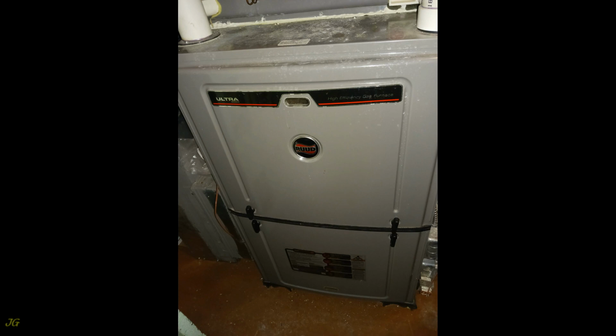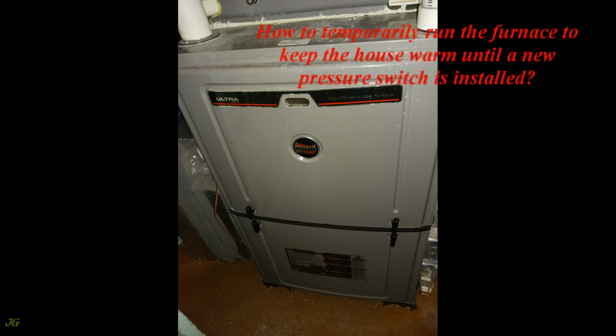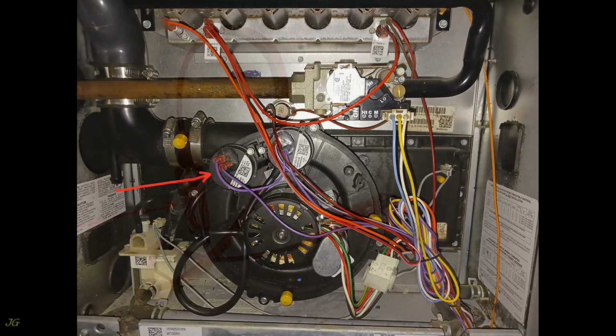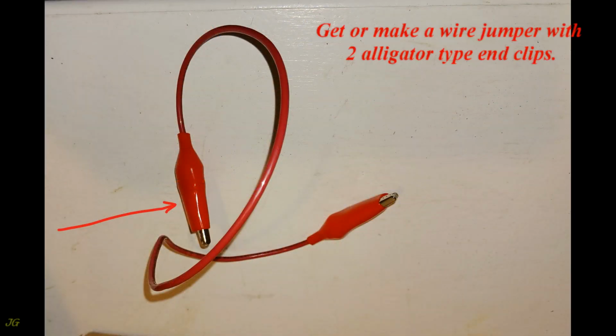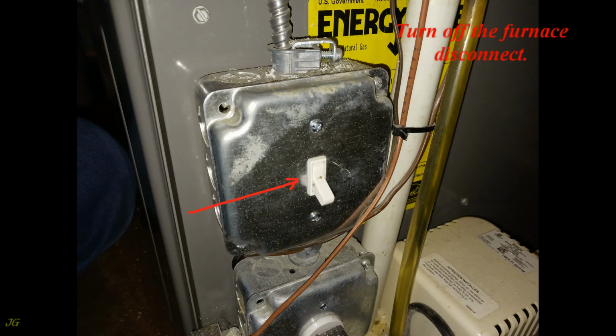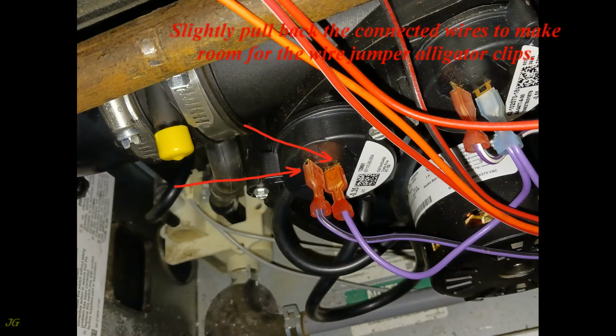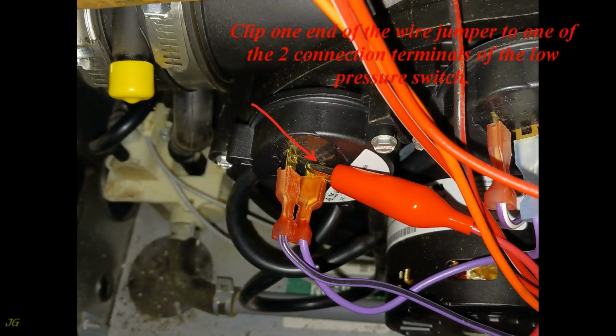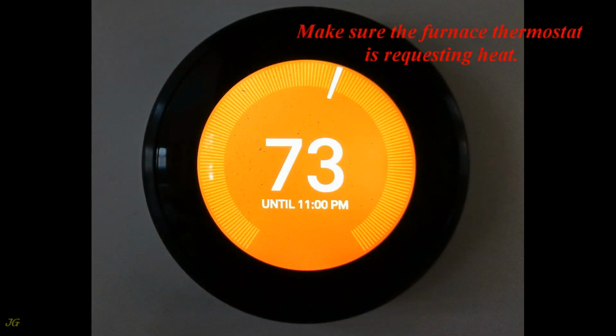How to temporarily run the furnace to keep the house warm until a new pressure switch is installed. Get or make a wire jumper with two alligator type end clips. Turn off the furnace disconnect. Slightly pull back the connected wires to make room for the wire jumper alligator clip. Clip one end of the wire jumper to one of the two connection terminals of the low pressure switch. Make sure the furnace thermostat is requesting heat.